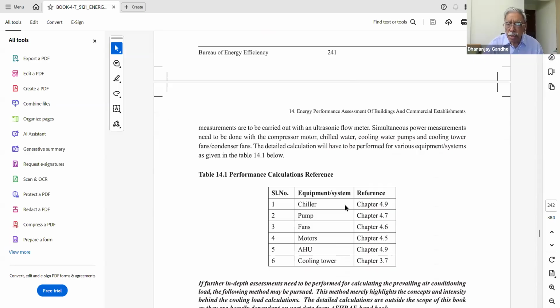load of that system, divided by the tons of refrigeration. This is the parameter to be worked out. So for the chiller and the pump and the fans and motor, you calculate what are the kilowatt per ton of refrigeration. So these four, five parameters are worked out to assess the performance of the HVAC system.